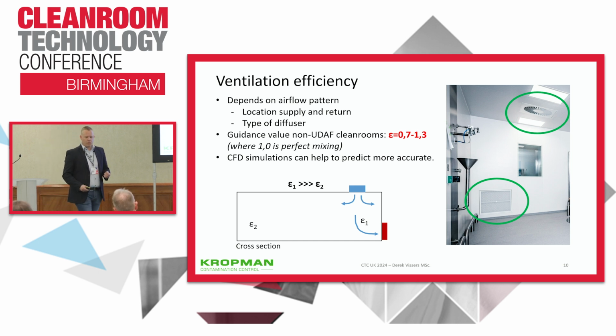So we found guidance values between 0.7 and 1.3 in our projects, and in literature also, where 1 is perfect mixing, 0.7 is worse but a good design value, and 1.3 is actually a really good value, and we found that in our clean rooms in the Netherlands where we measured it, meaning that the local air change rate is higher than the average air change rate in your clean room. Of course, CFD simulations can help to predict those values more accurately, but CFD simulations also have their limitations, and the output is highly dependent on the quality of the input.